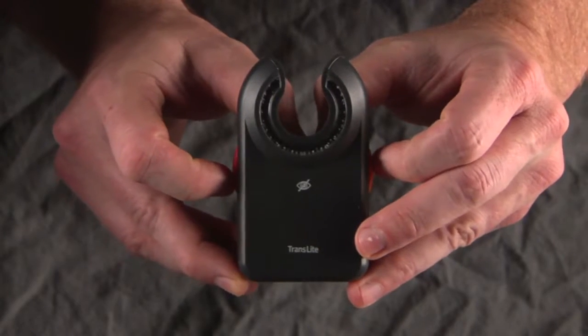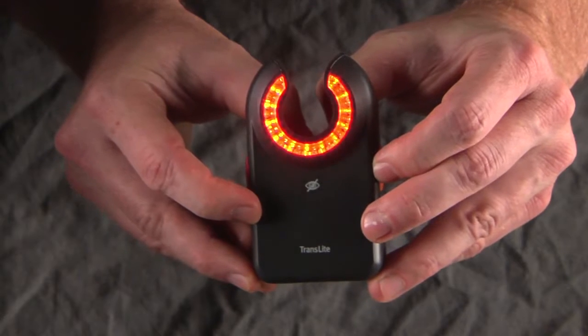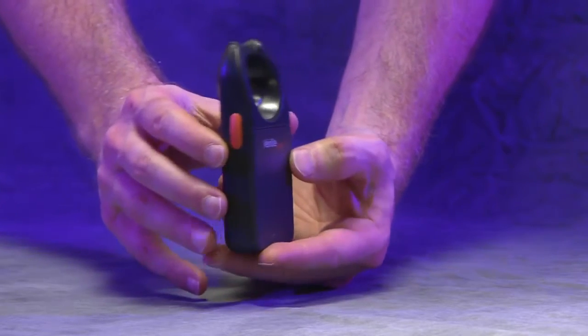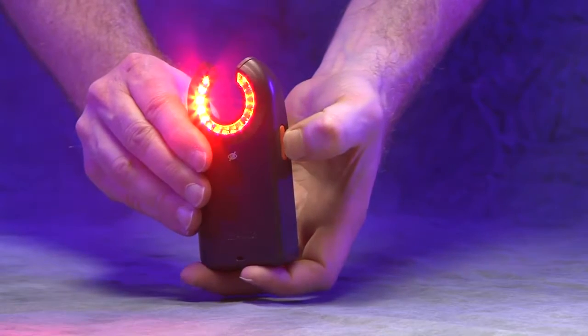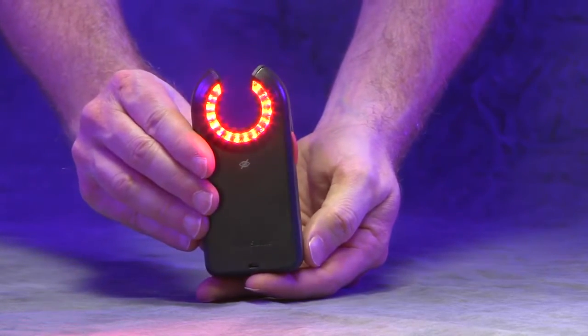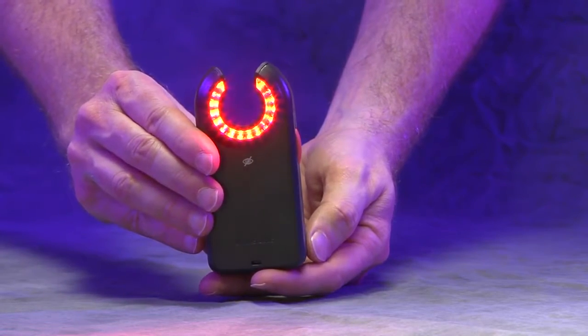You can also activate both the orange and red LEDs if a higher contrast is needed for vein illumination. If only one button is available on your device, it will activate the orange and red LEDs at the same time. While this simplified setting is designed to work with all skin pigmentation types, it will not provide the same contrast options of a two-button device.